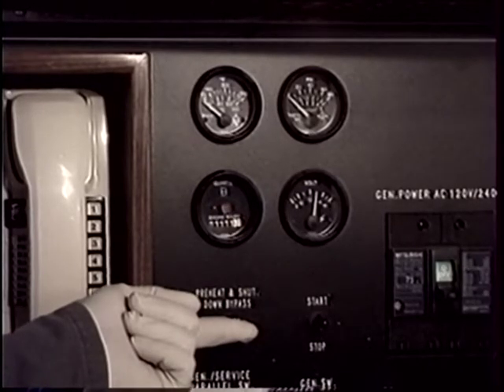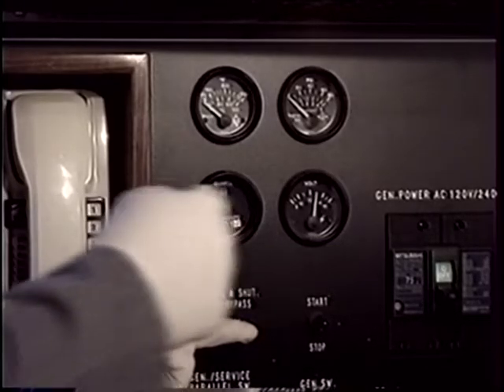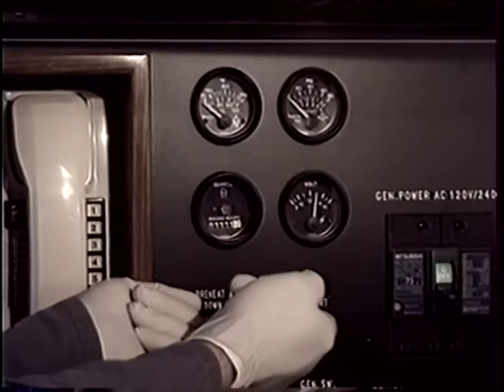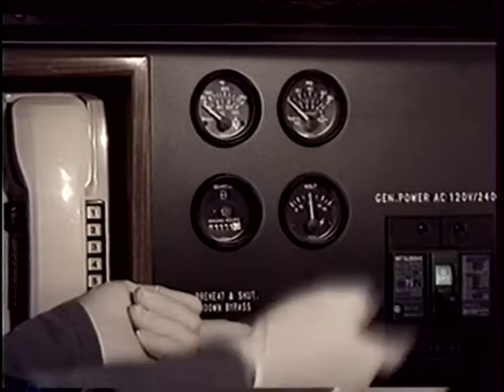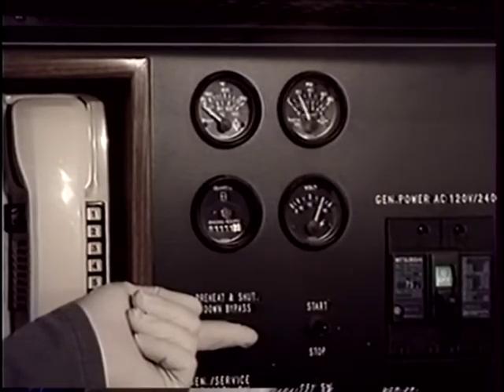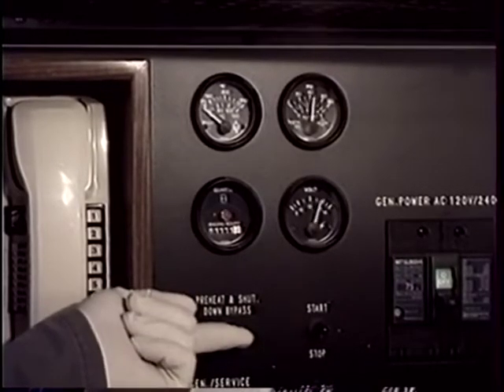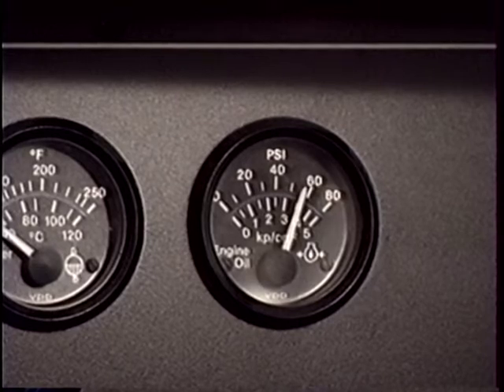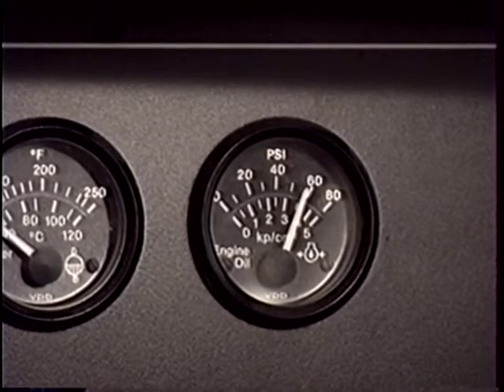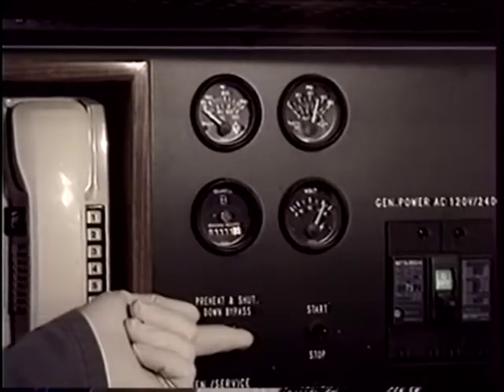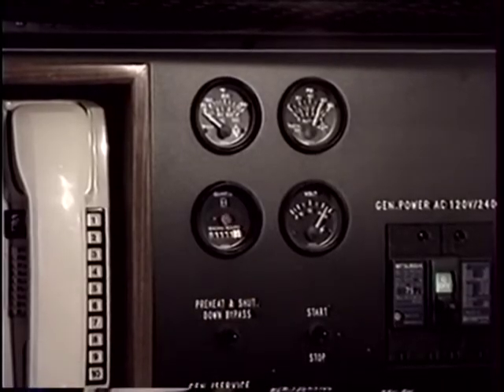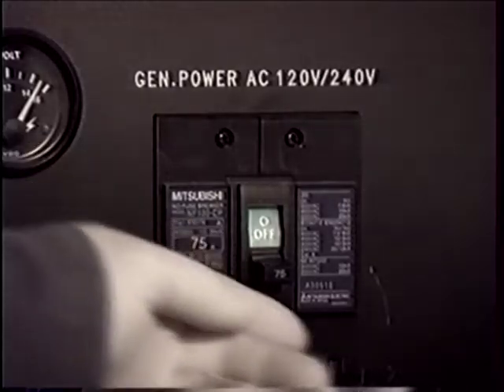fuel solenoid. While continuing to hold the preheat switch, push the starter switch to crank over the engine until it starts. Continue to hold the preheat switch until oil pressure has developed. Generally, this will take about 10 additional seconds. Release the preheat switch. You can now close the main circuit breaker or generator load selector switch.